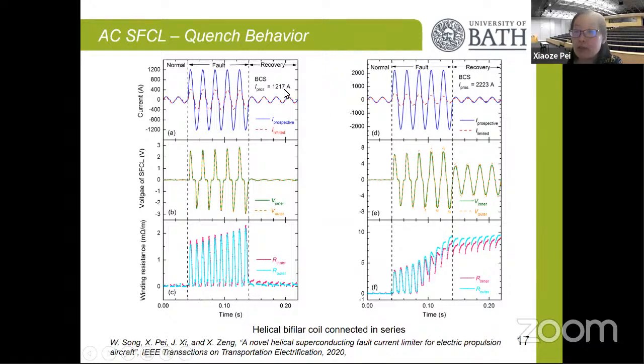When the fault current is just a few times the critical current, you can see this is a fault for 100 milliseconds. When the fault is removed and it goes back to the recovery current, similar to the normal current, you can see under this condition the superconducting fault current limiter is able to recover very quickly to its original state. So if a fault happens, it can go back to limitation, and the resistance goes back to this level.